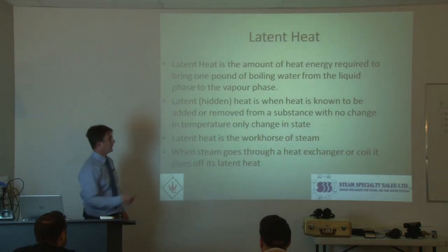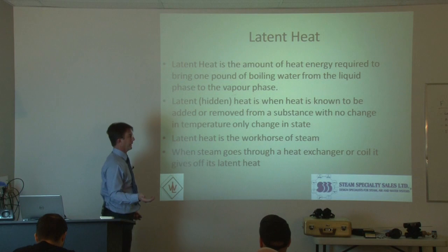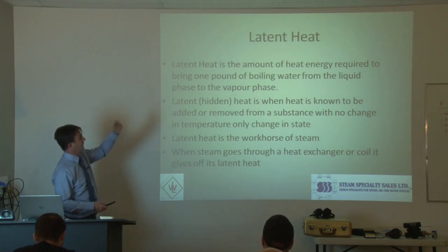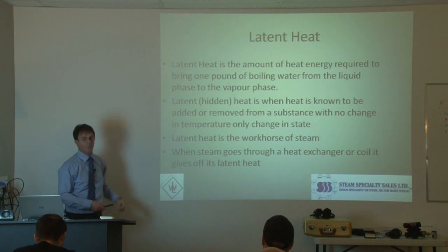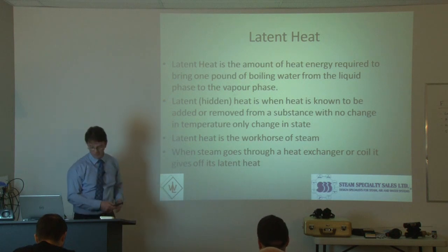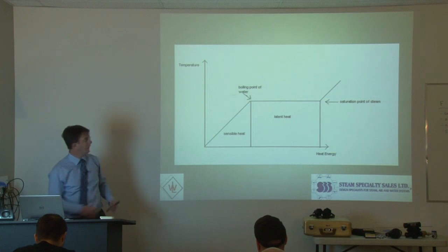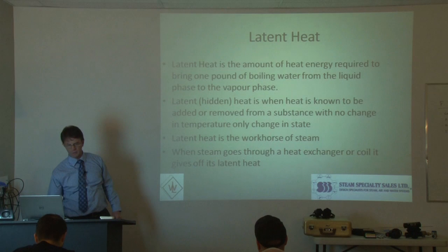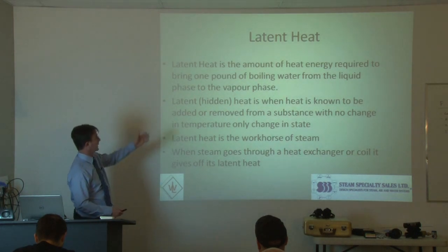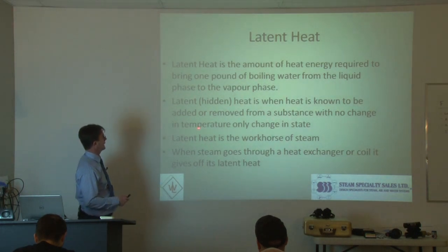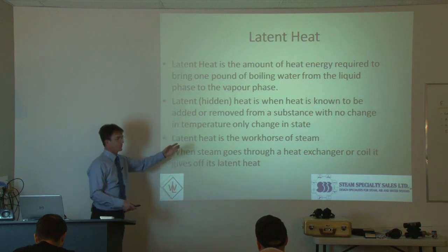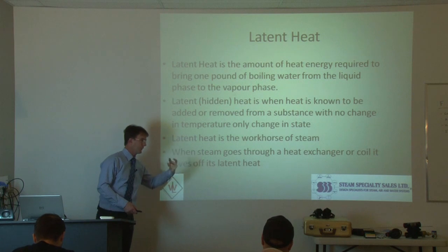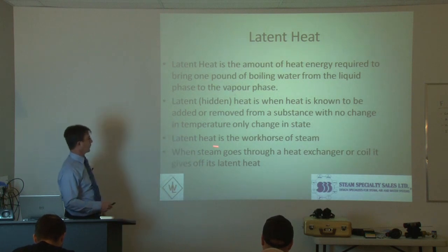The latent heat — latent is another word for hidden, so it's like hidden heat. Hidden heat or latent heat is the amount of heat energy required to bring one pound of boiling water from the liquid phase to the vapor phase. So right here, we don't have steam yet. We're just bubbling boiling water, so we haven't changed phase yet. Latent heat is when heat is known to be added or removed from a substance with no change in temperature, only a change in state. So we're going from the liquid phase into the vapor phase.